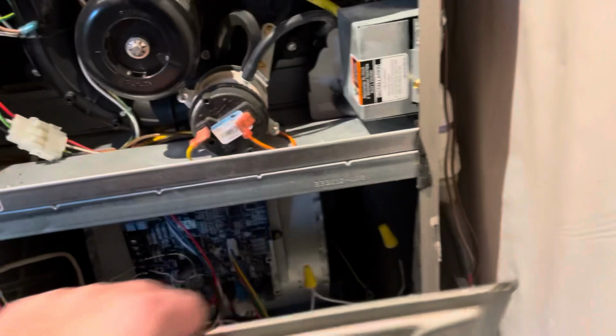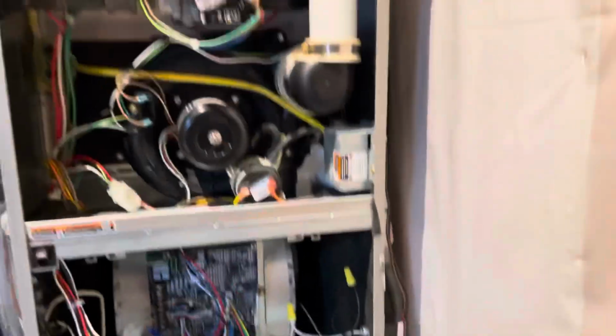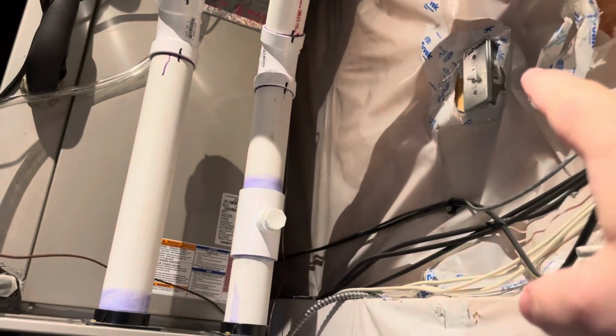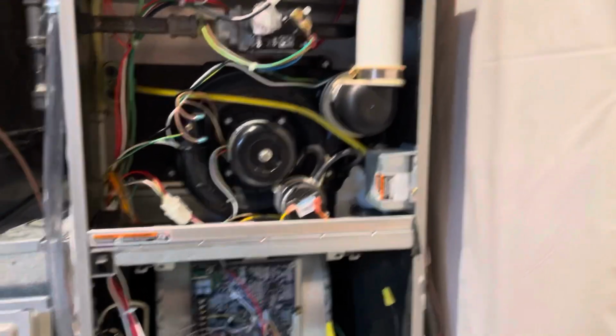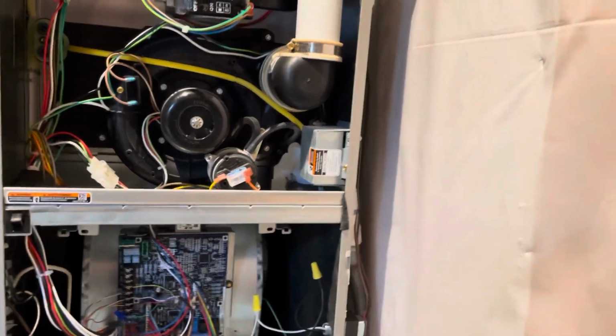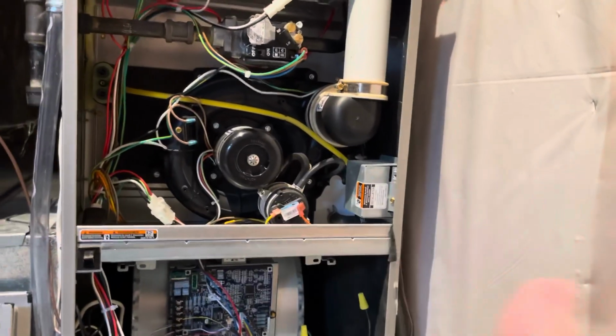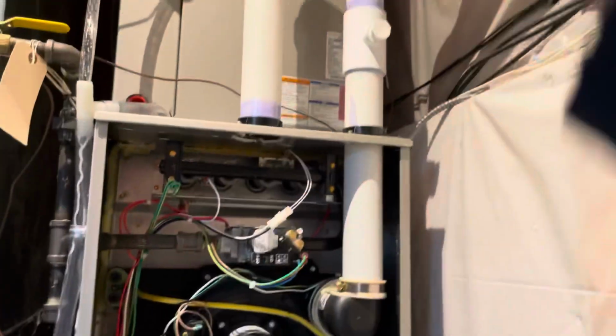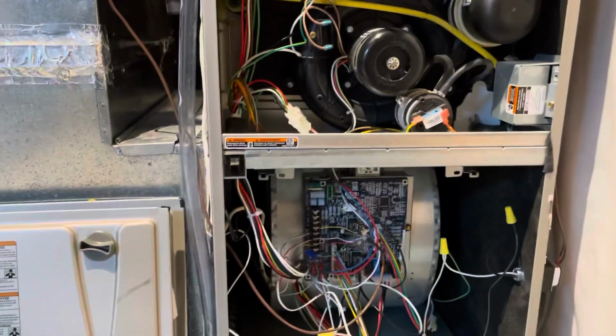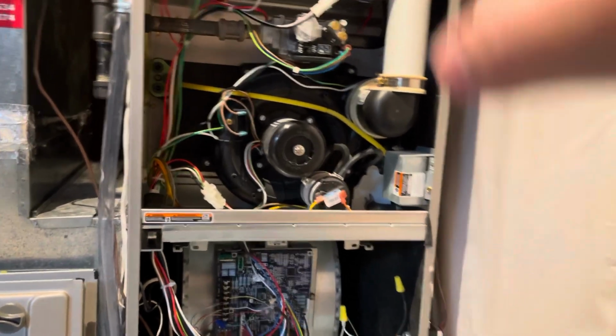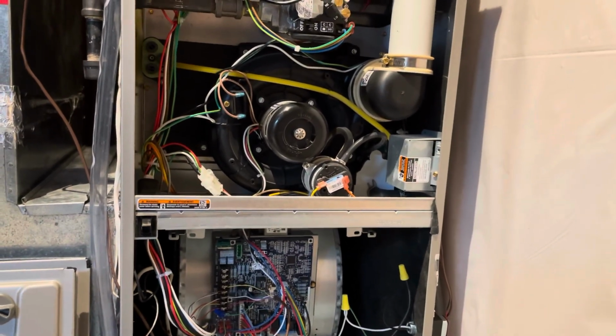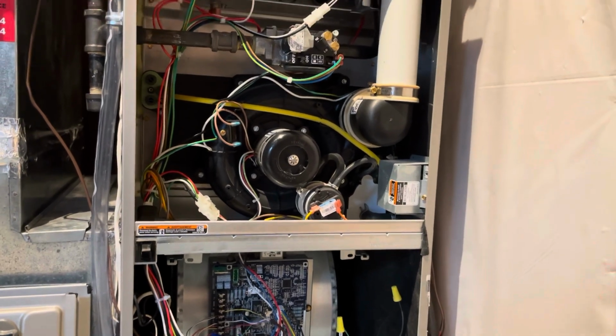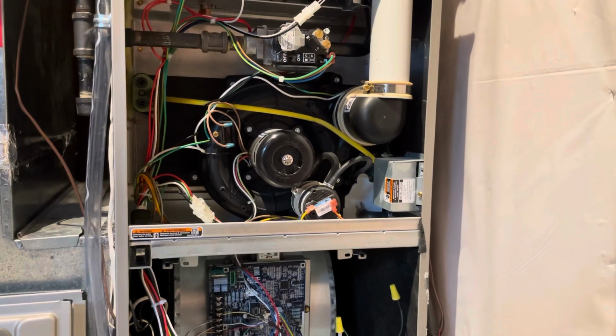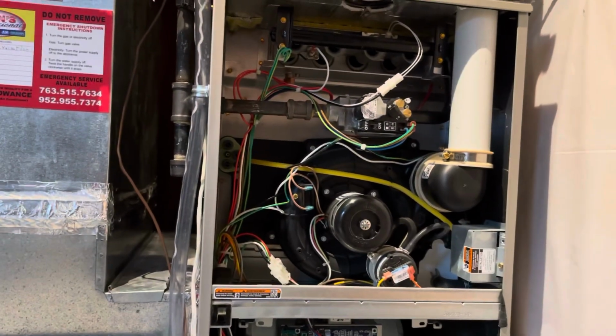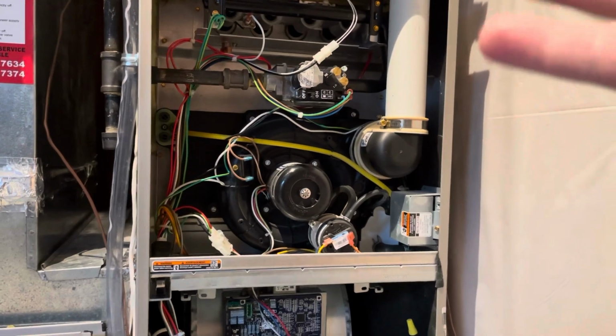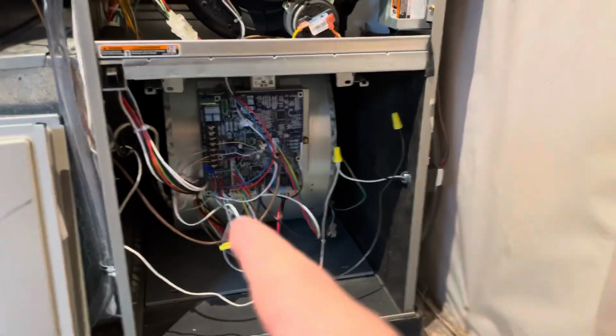I have seen some people wire the transformer straight into either their furnace on/off switch or an outlet. That's one option, but I wanted to set mine up with the EAC so that whenever the blower motor kicks on, it will kick on the humidifier too and call for humidity, so that I'm not limited to just when the heat runs. I wanted that option to have humidity flow throughout the house when we just have the fan on, or to have the humidistat trigger the humidifier and the blower fan without necessarily calling for heat, so I had to hook the transformer up to the EAC.